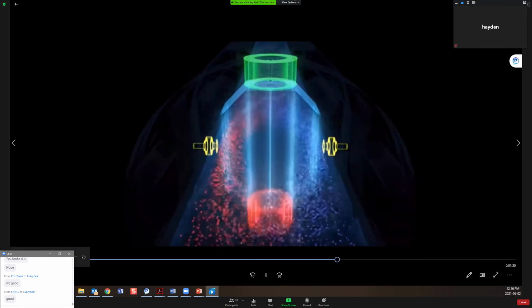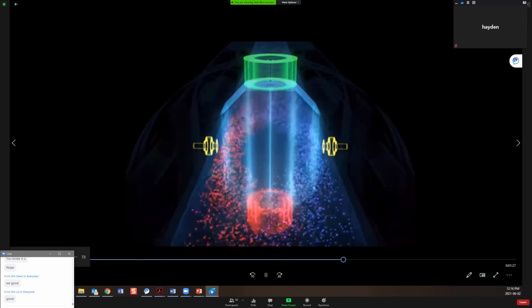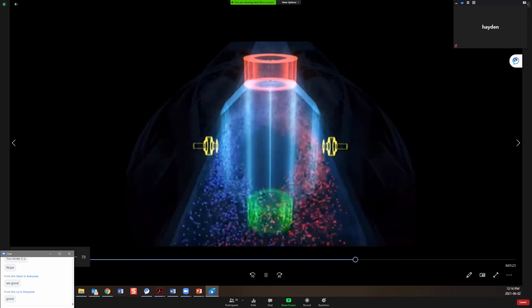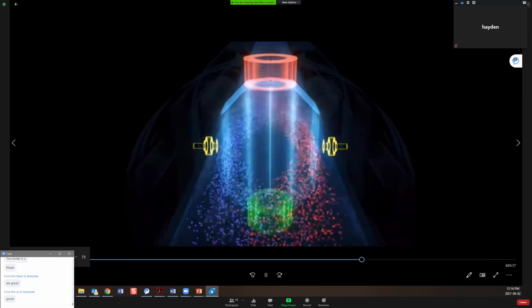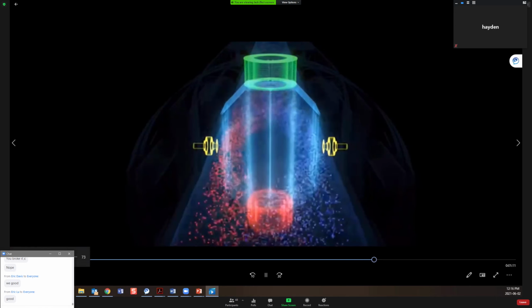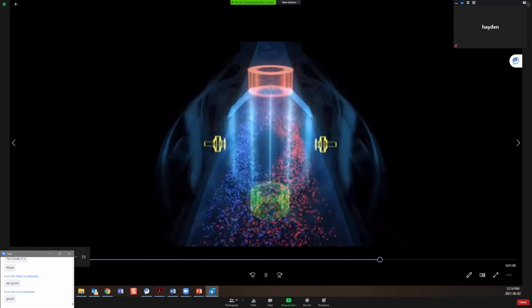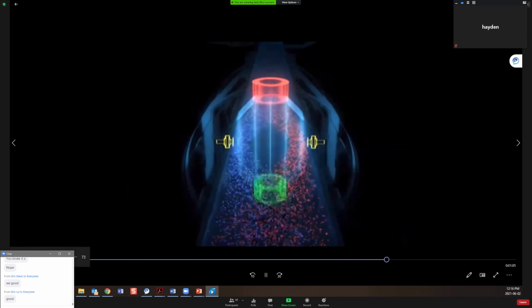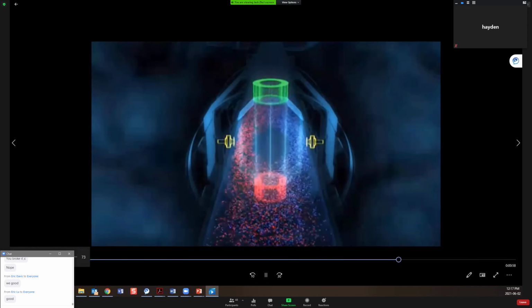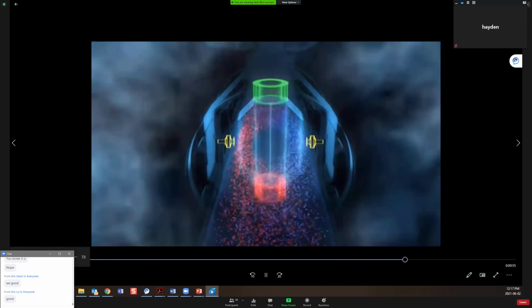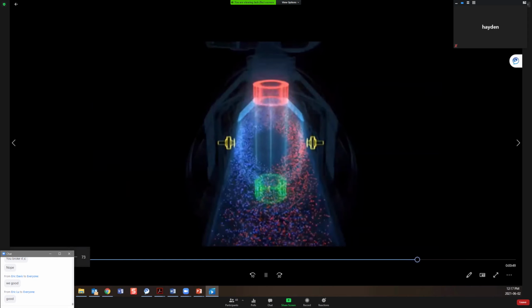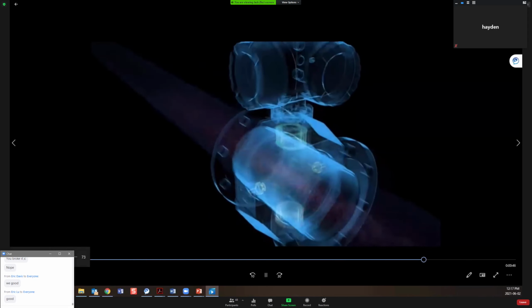One method that has been successfully used for this purpose is to create the magnetic field with a pulsed direct current. To do so, the polarity of the magnetic field is alternately reversed, illustrated here in slow motion. The voltage picked up on the measuring electrodes now constantly changes in polarity. As a result, all constant interference voltages can be eliminated, for example electrochemical effects in the liquid, or external electromagnetic fields. Thus, the size of such interference voltages has no impact whatsoever on the actual measuring signal. The advantages of this are a stable measurement and a stable system zero point.